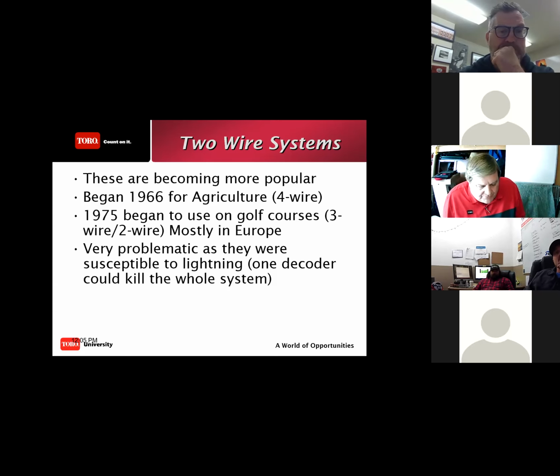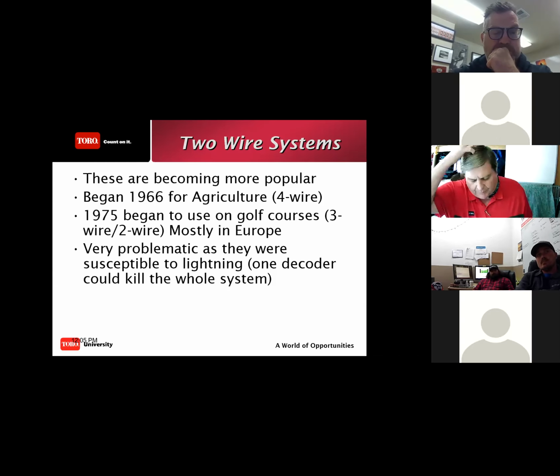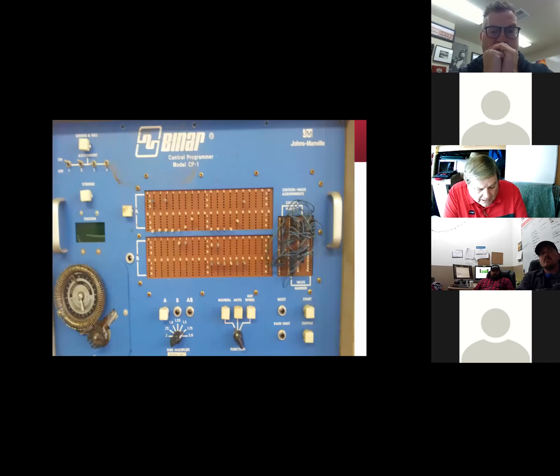And that's how the very first two-wire system was. You had a bad decoder, and the entire system went down because of that one decoder. And then you had to go through and try and figure out which one it was. So they lost a little popularity at that point. In Europe, another company came up with another way of doing it, much like our new Christmas light strings, where one bulb dead, you know which bulb it is. And it became more popular at that point and started to see them become more popular as time went on.